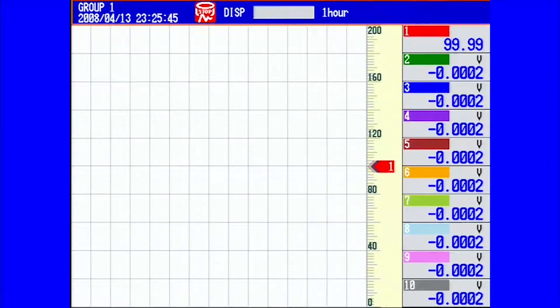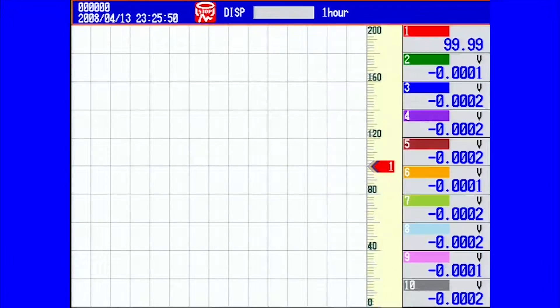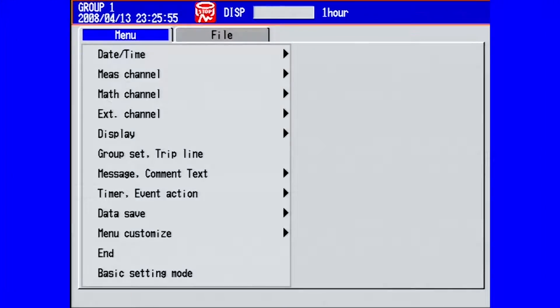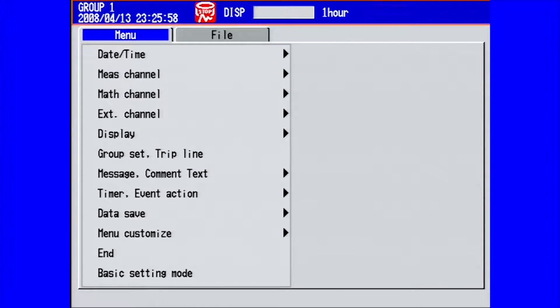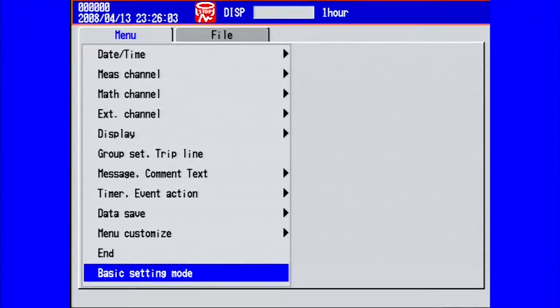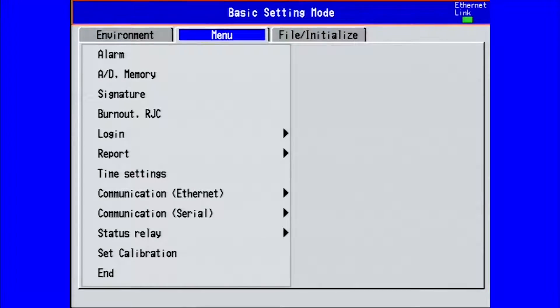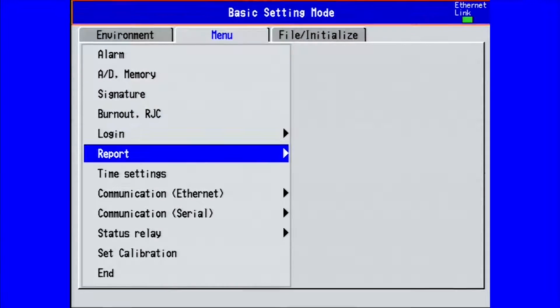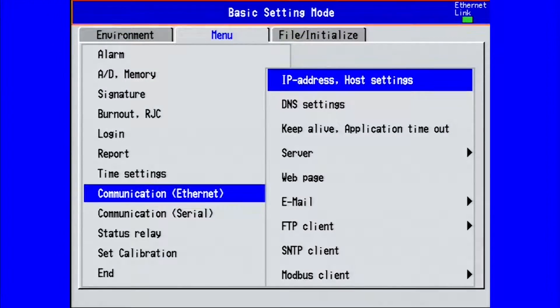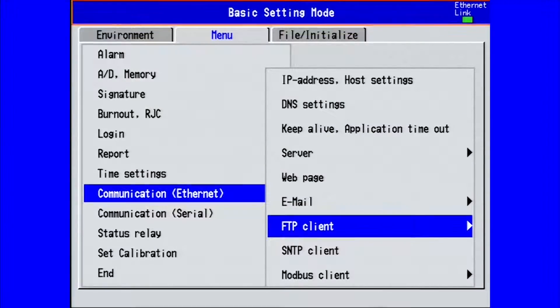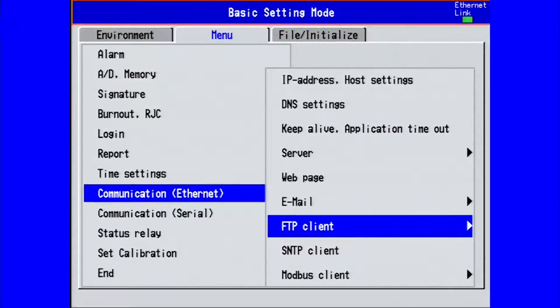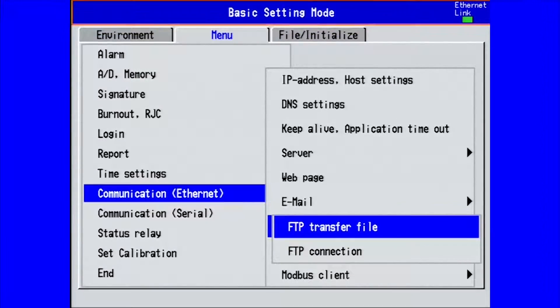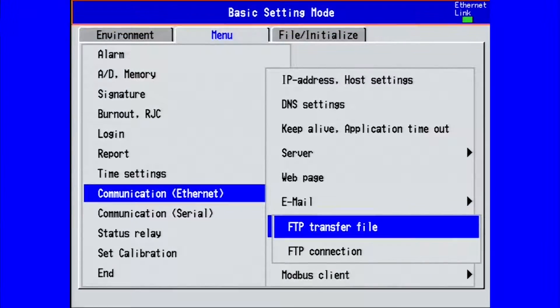Now we will set up our FTP client settings in our DX2000 data acquisition station. To do this, you would press the menu key, then go to basic setting mode or hold down the function key for three seconds. Under the menu tab, go to communication ethernet, right arrow key, and down arrow key to FTP client, and press enter. The two options are FTP transfer file and FTP connection. We will look at the FTP transfer file first. Press enter.